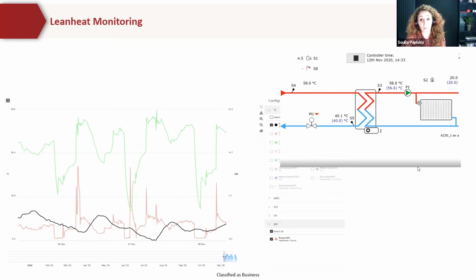So what this is showing is that without weather compensation, you would have a fixed flow temperature, which in 99% of the cases would be too much. By using weather compensation functionality, you start to create energy and money savings through your equipment. A minimum temperature can be set during weather compensation to ensure that your domestic hot water demand is achievable. And I know that the domestic hot water side of a network is so important, and in the previous presentations you would have heard as to why that is. And while weather compensation appears to be a very low level control, there are very few systems that I see in the field that actually use this functionality of control. By using a data-driven approach and a smart software, like Lean Heat Monitor, this would automatically be a function rather than something that needs to be manually set.